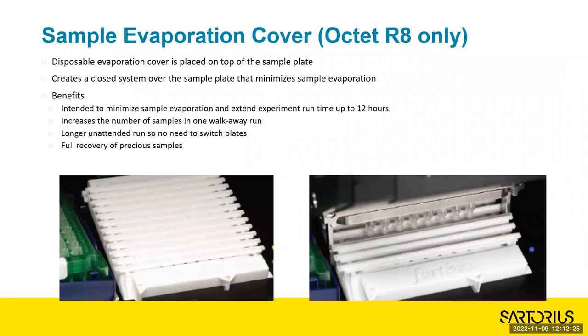If you are working with really tight binders, it can take a very long time for them to dissociate so you can calculate an off-rate. The longer the dissociation, the longer the assay will take. You might run into an evaporation problem once you get to four or five hour assays. So we've designed an evaporation cover to sit on top of the 96-well plate with a shutter system - two rods push one shutter down, exposing a single column at a time. You can lengthen your assays up to 12 to 18 hours without evaporation problems.